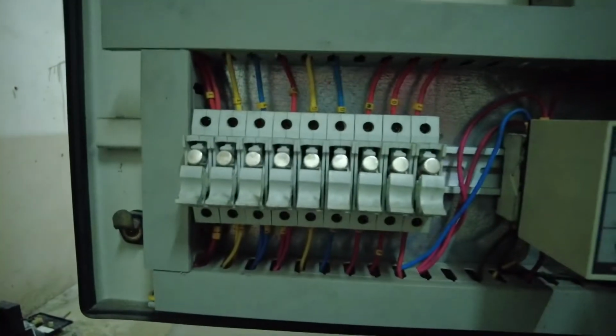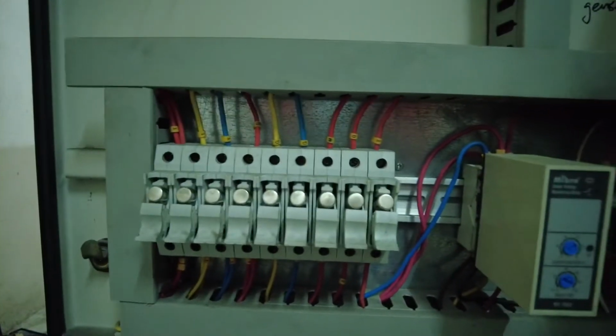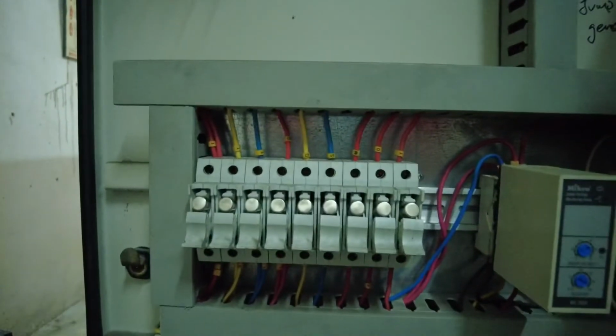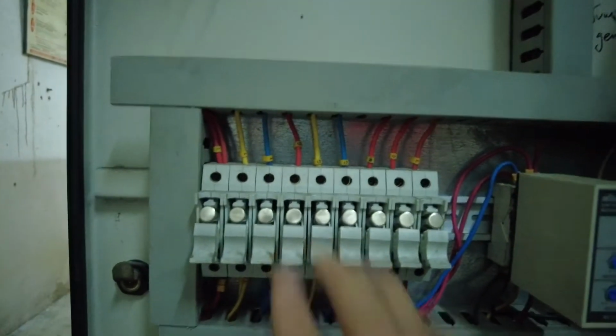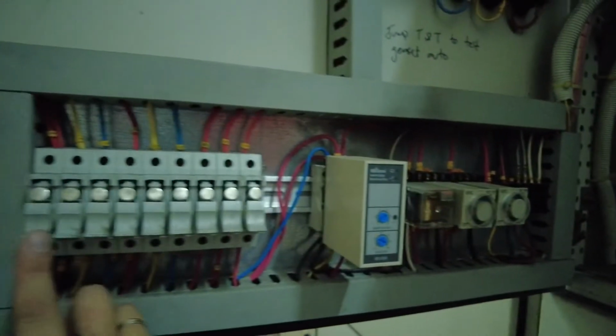We normalize the fuse to allow it to stop automatically. Just then it had start automatically. So without any triggering from the AMF panel, we just allow it to happen. Allow it to on and allow it to off automatically. Alright. Okay, here we have the fuse, all the control fuse. Just then we manually off. First of all, don't put back the genset fuse first. Put back the main supply fuse first. Let this thing operate first.